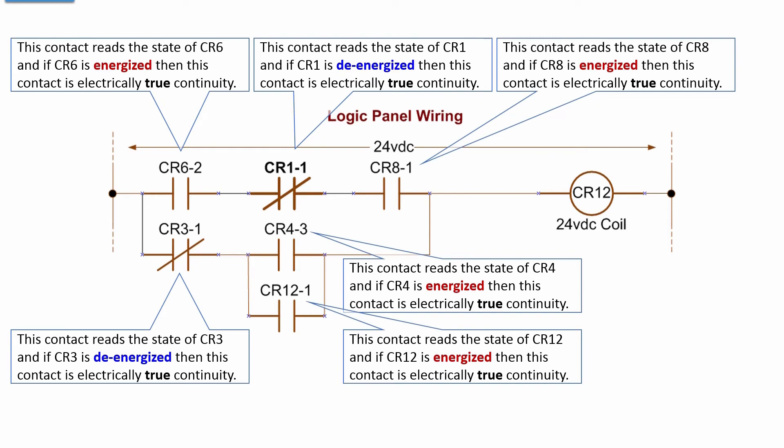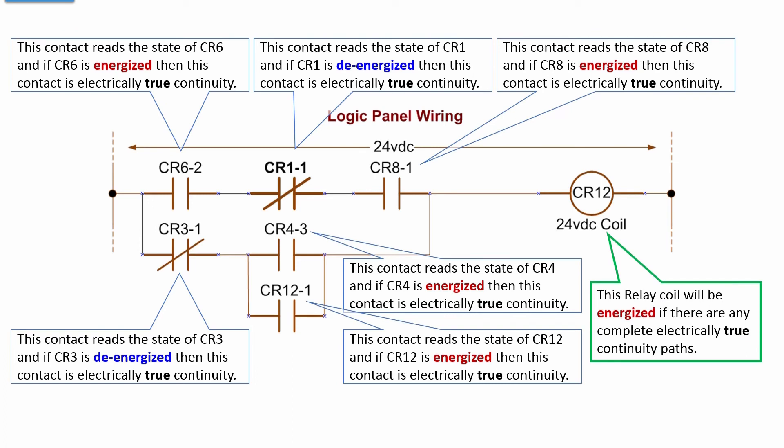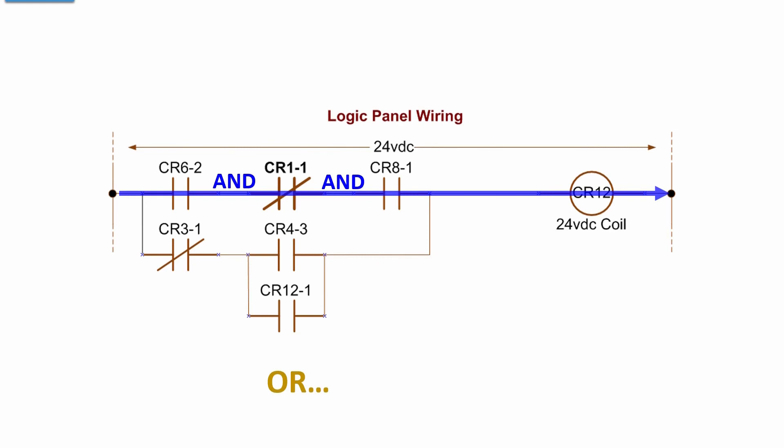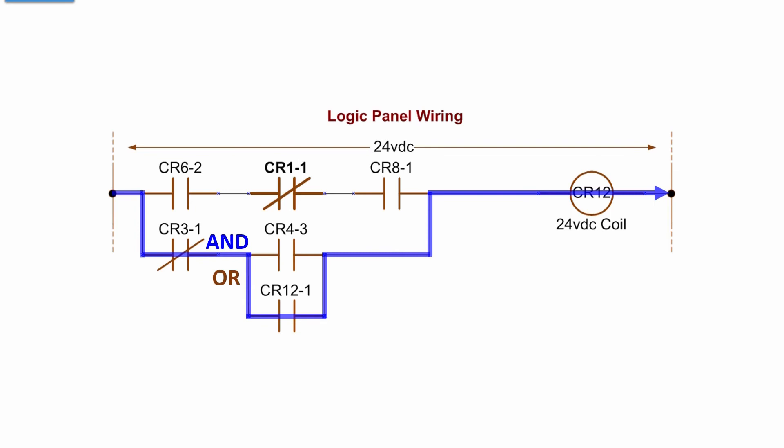Any logically true path through this set of contacts will energize CR12. How many possible true paths of electrical continuity do we have? Here's the first: if CR6 is energized, and CR1 is de-energized, and CR8 is energized, then energize CR12. Or if CR3 is de-energized (off) and CR4 is energized, then energize CR12. Or if CR3 is de-energized and CR12 is already energized, then keep CR12 energized — that's the seal-in path.